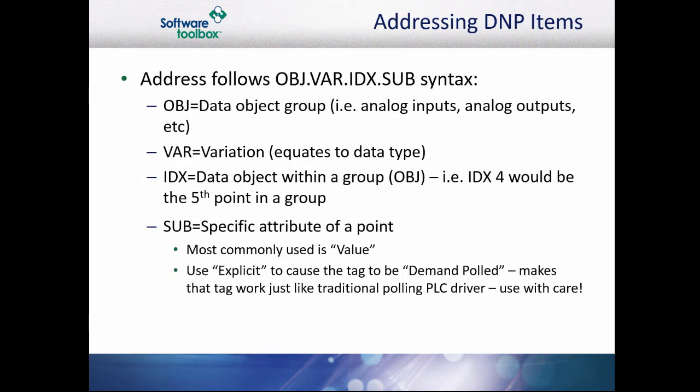DNP3 items are addressed with a four-part address: object.variation.index.subtype (or subattribute). The object is the data object group to which the item belongs. Variation defines the default data type for the item. Index is the data object within the group — for example, the fifth point in the group would have an index of 4 because indexing, as well as variations, start at 0. The subattribute or subtype is the attribute you wish to read for the specific index or point. Most often, you will use dot value to read the index value.